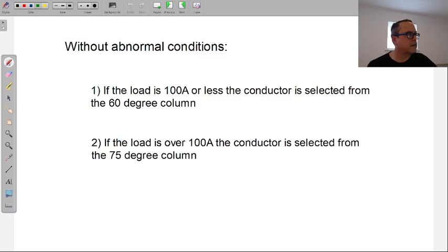Let's see here if I can find it. If it is 310, then it should be right after the table of insulation, if I'm not mistaken. Capacities of insulated conductors with not more than 3 current-carrying conductors. And then also, this was what was written down from Code A. It says for the circuit breakers, refer to 240.6. Yes, that's the size to size the circuit breaker. We got that part. I'm just trying to find the literal words from the article.